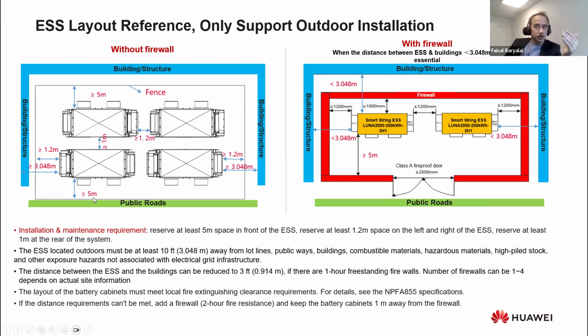Some of these distances, like the one in front of the ESS, are mainly for maintenance access and for using a forklift to place the battery during installation. This distance could be up to 5 meters, but if space is limited, you could use fences that open during maintenance and close afterward, so the distance in front of the battery could be less than 5 meters if space isn't available.